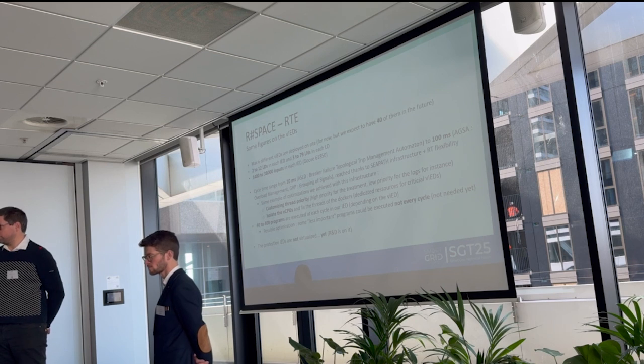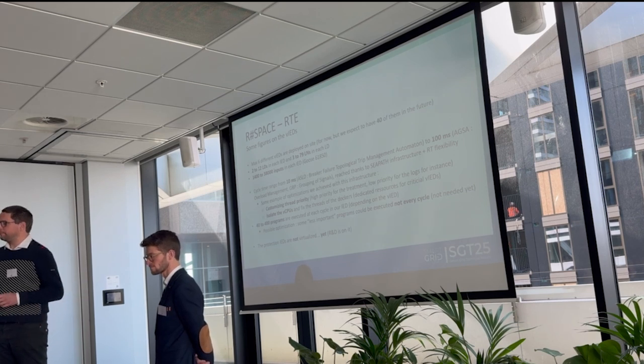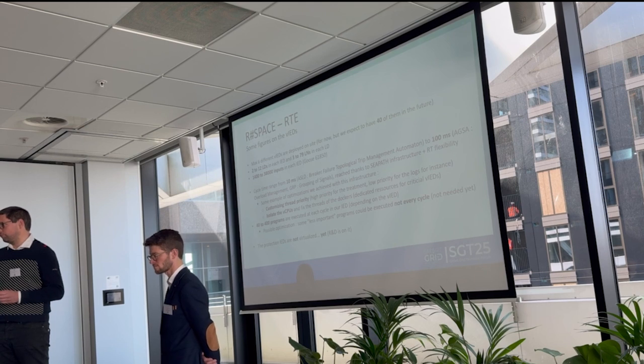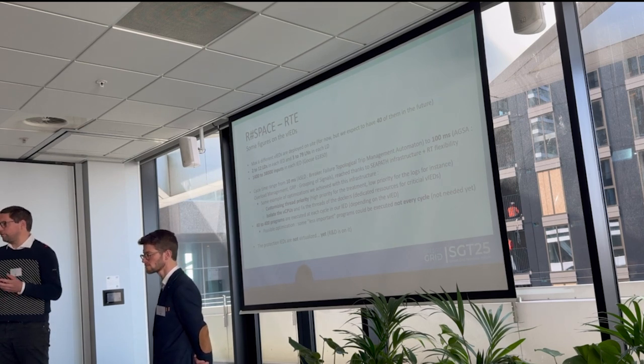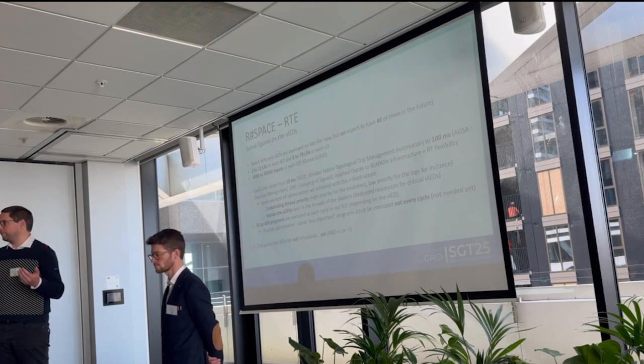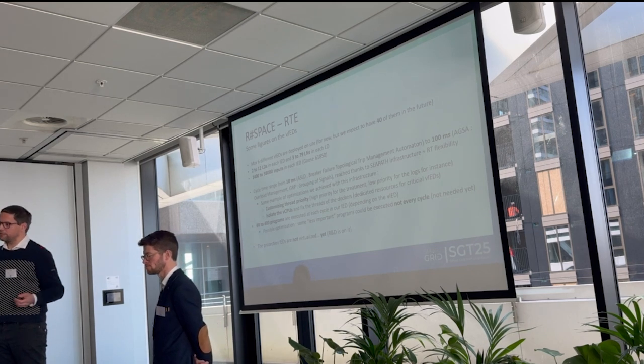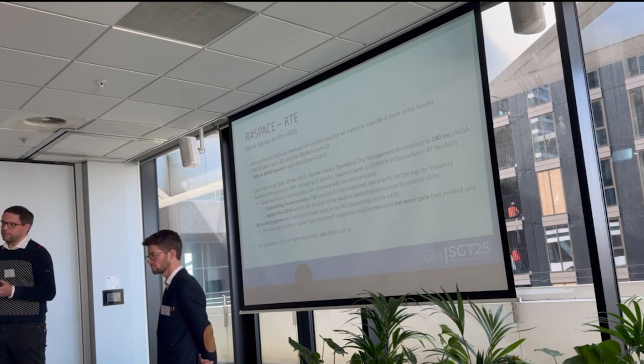So we asked Straton to have a 10 millisecond time cycle between each cycle of the PLC. It's a virtual PLC. And basically, if we are over it, then we have a log. That's a simple way, in fact. We have a log saying we are over the time cycle configured. It may be 12 milliseconds, 100 milliseconds, I don't know. So it's quite easy to see.